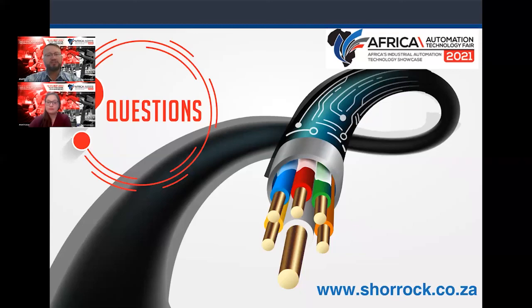And then the last thing that I'd like to add is it's got a communication module. This enables us to then pull data from the device and actually directly into the PLC. In the past, most of the products out in the industry, even our previous products, only had a digital input connected to the device, and we could only get a state saying that the device is in an overload condition or the device is off. But you can see it's off, the PLC is also off.